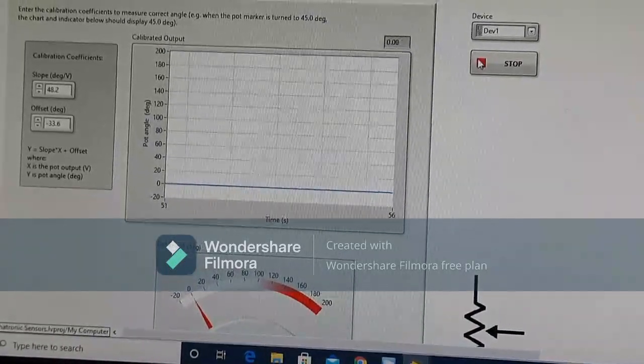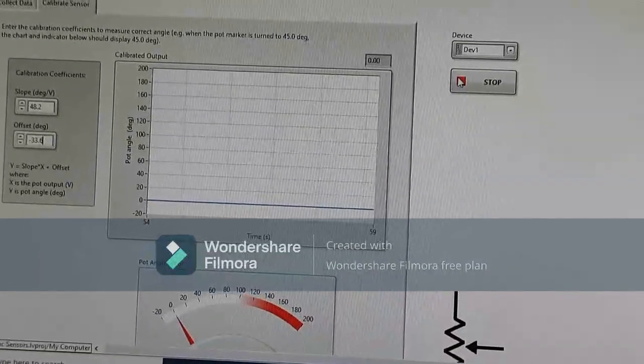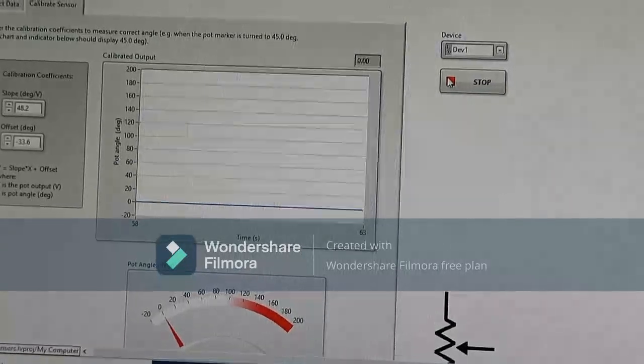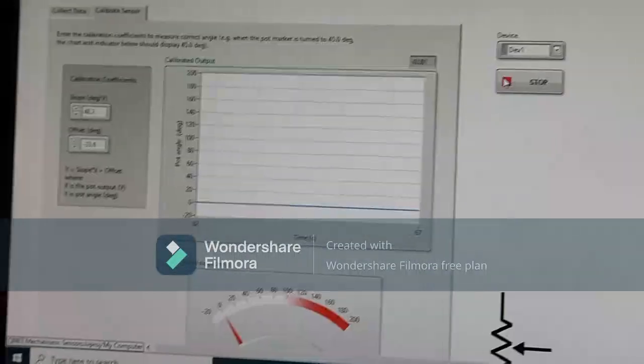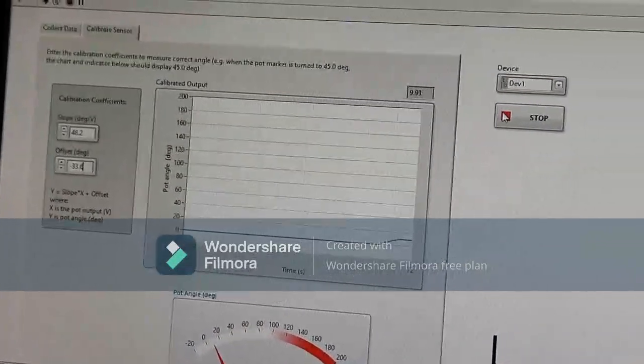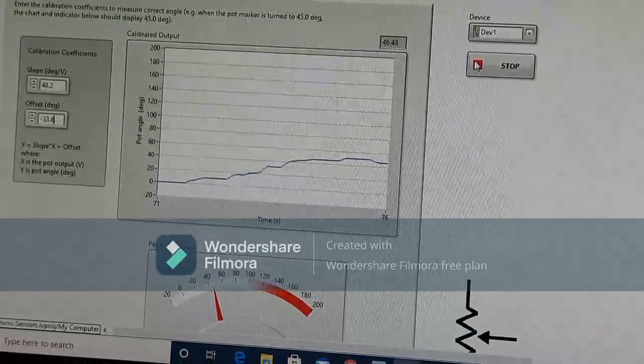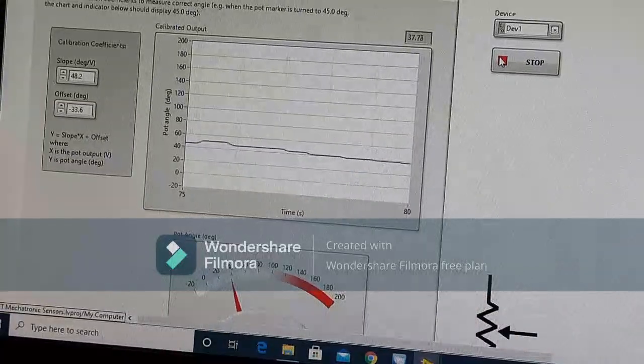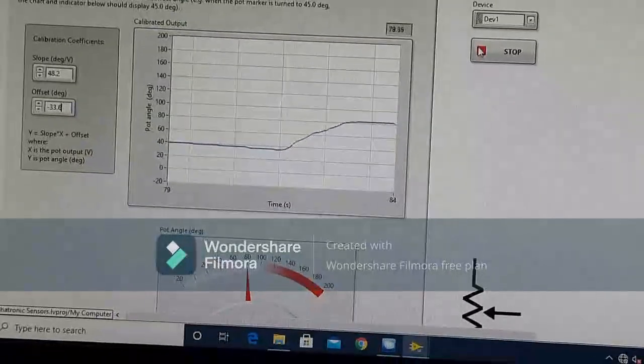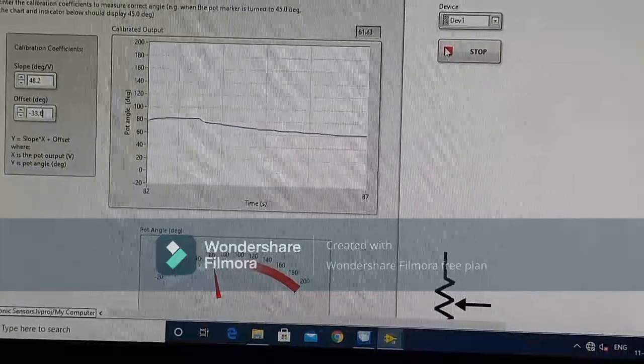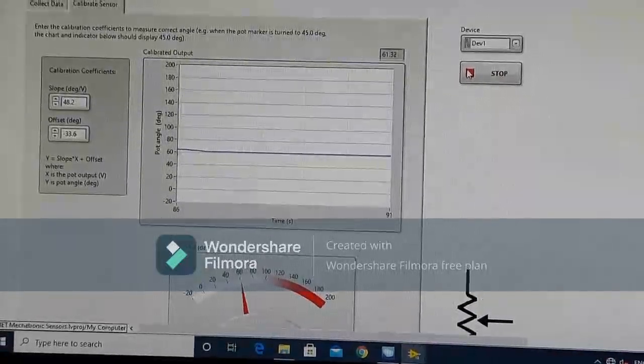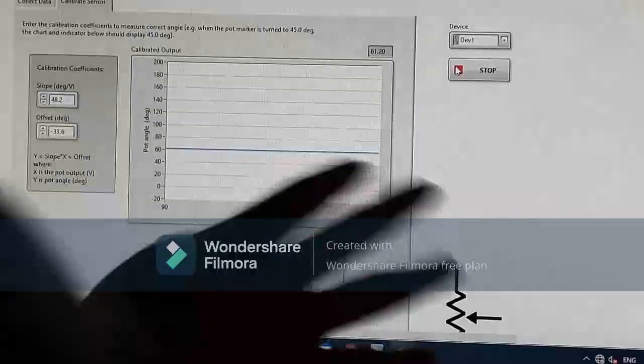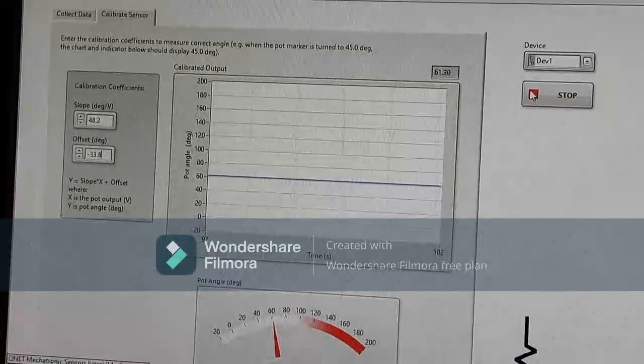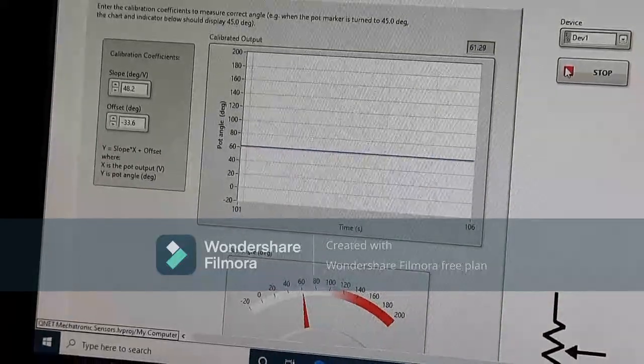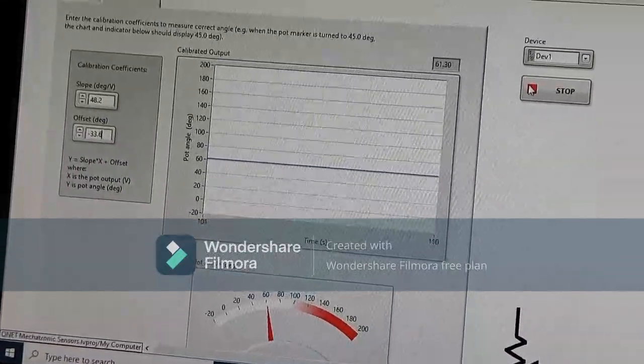After the calibration is done, we should get the exact output. The amount of input which we are giving, the output should be exactly the same. Fine. Some values, let's see. Okay, now it is at 60 degrees, and you can see some values, might be because I cannot match the position properly. It is showing 61 point something, 3 or 2 maybe. Fine. So it is almost calibrated. Some error will be there because I can't move the knob exactly to the same position.